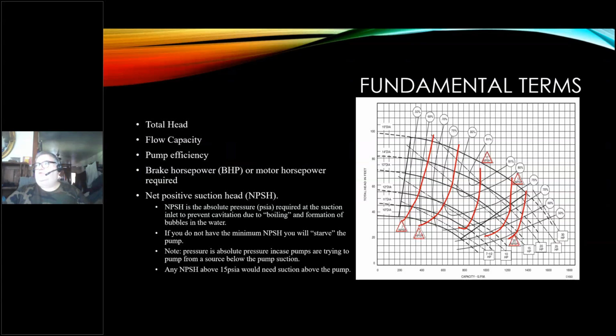Usually a strainer, somebody closed a valve on the inlet side, or in some cases you've lost water and didn't make it up. So you actually have air trapped in the system somewhere that's fooling the system into thinking it's got water, but you really don't have enough water. Any net positive suction head above 15 psi would need suction above the pump in this case. In other words, you would have to put that suction above the pump, that pressure, to get a vertical head coming in to actually improve it, because 15 psi is atmosphere. So if you were trying to pull water into a pump and you saw a negative 15 psi, that's as best as you're going to get, and you're not moving any water.